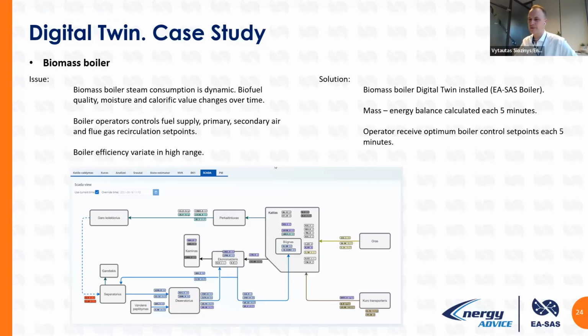It is absolutely the same with a biomass boiler. We take all the SCADA data from the controllers, from the SCADA system. We build the biomass burning, energy flow, and energy exchange mathematics, and what we are capable of doing is calculating fuel mass consumption, mass and energy balance. We are capable of calculating water content in the fuel, calorific value in real time, efficiency in real time, and providing set points for the fuel supply, primary, secondary, and tertiary air supply. If you have flue gas recirculation, it would be flue gas recirculation. If you have a boiler with a grate, you would provide grate rate set points, how it should be in your system. And your operators, looking at our system, would adjust your boiler parameters for the best performance.